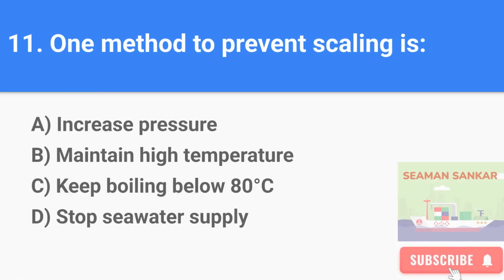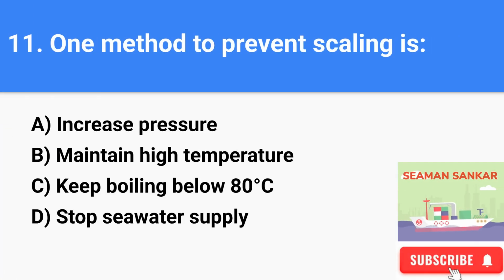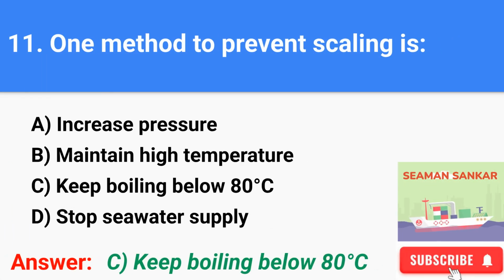Question 11. One method to prevent scaling is A. Increase pressure, B. Maintain high temperature, C. Keep boiling below 80 degrees Celsius, or D. Stop seawater supply. The answer is C. Keep boiling below 80 degrees Celsius. This minimizes the precipitation of calcium carbonate, a major scale component.